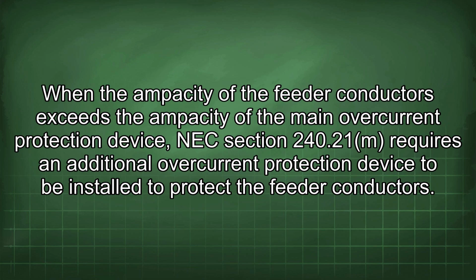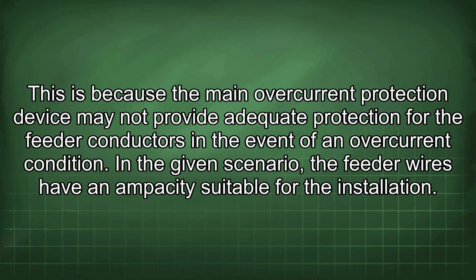When the ampacity of the feeder conductors exceeds the ampacity of the main overcurrent protection device, NEC Section 240.21 requires an additional overcurrent protection device to be installed to protect the feeder conductors. This is because the main overcurrent protection device may not provide adequate protection for the feeder conductors in the event of an overcurrent condition. In the given scenario, the feeder wires have an ampacity suitable for the installation.